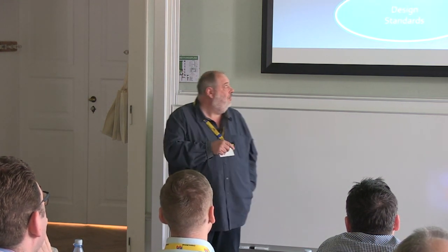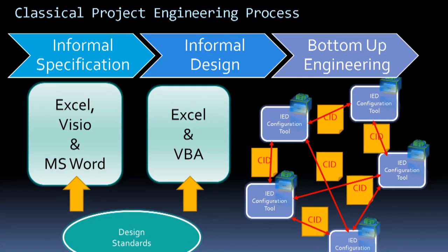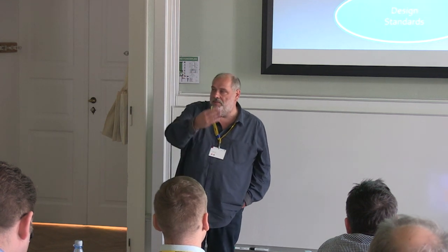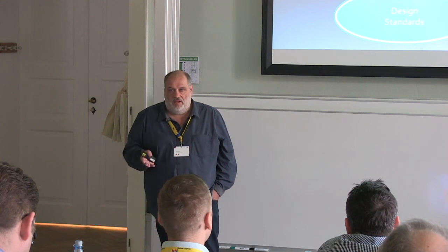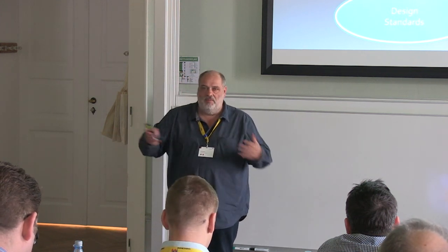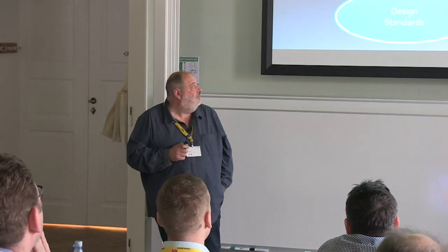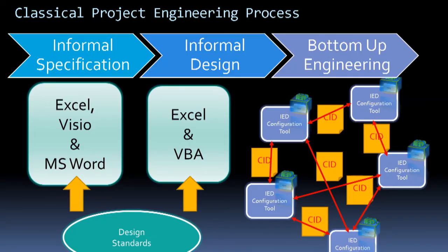But basically the people fall back to a purely CID-driven engineering. It's obvious that if I have hundreds of IEDs, if I combine several substations, it is a very lengthy and error-prone work to make publishing and subscribing for each IED. In a lab environment, this works very well. I can make interoperability between 4 or 5 devices using the relay tools, and after a couple of hours or days it works. In a big system, it's really very, very hard to maintain and do this. So that is the reality today.